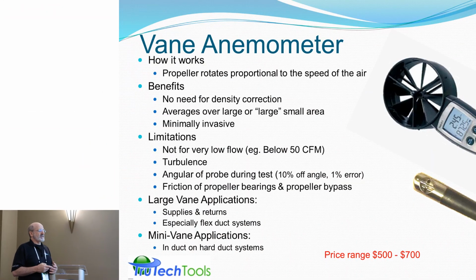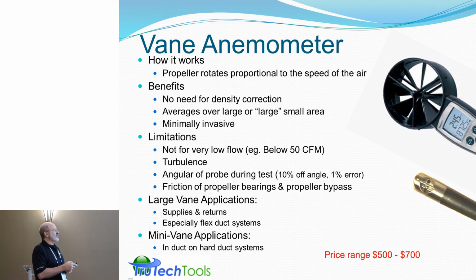Vane anemometers, we talked a little bit about those. Roger had mentioned the propeller rotates proportional to the speed of air, so it's not about density. There's no need for density correction. And they average over a large area, like 4 inches in diameter, or I call it a large small area. It's larger than a pitot tube. It's larger than a hot wire. I think it's about 1/2 inch diameter for the mini vane that it's averaging over. So it's accommodating more information to give you a better average number more quickly.